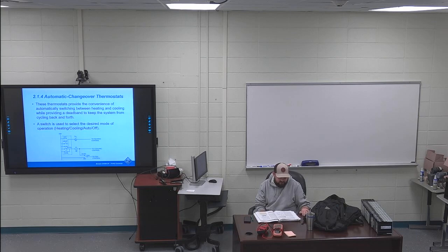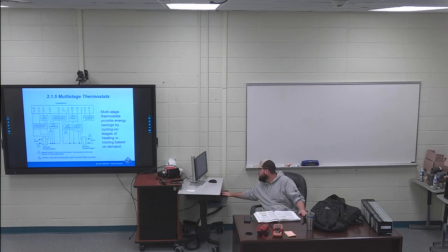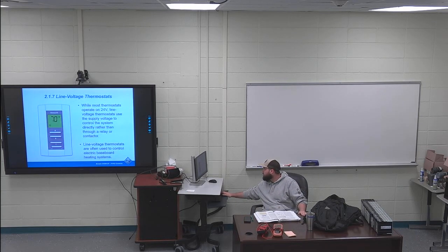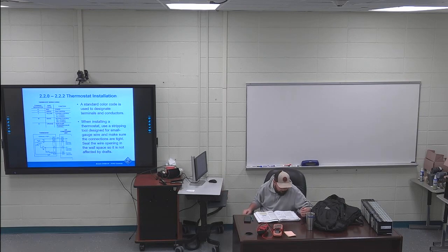On page 16, the first paragraph, third sentence is highlighted. Locate the thermostat in wall plane or sub base about 5 feet above the finished floor in an area with good circulation at room temperature. So this is on an interior wall.